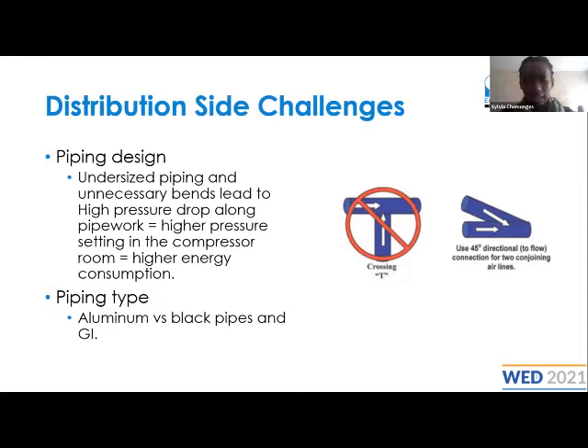Anyway, we'll get into the solution side. Another thing that we see at site on the distribution side is the type of pipe. You might go to a food industry, where the compressed air ends up interacting with products that you're going to consume, so it has to be of very high quality. You'll end up meeting companies using GI. GI or black pipes are very prone to rust. Imagine carrying that rust and the condensate within the system into your products, and you'll end up having a lot of issues meeting the required standards. You might be told to go back and fix products again. So you'll end up losing more by using the wrong pipe material than by selecting the correct type for your application.